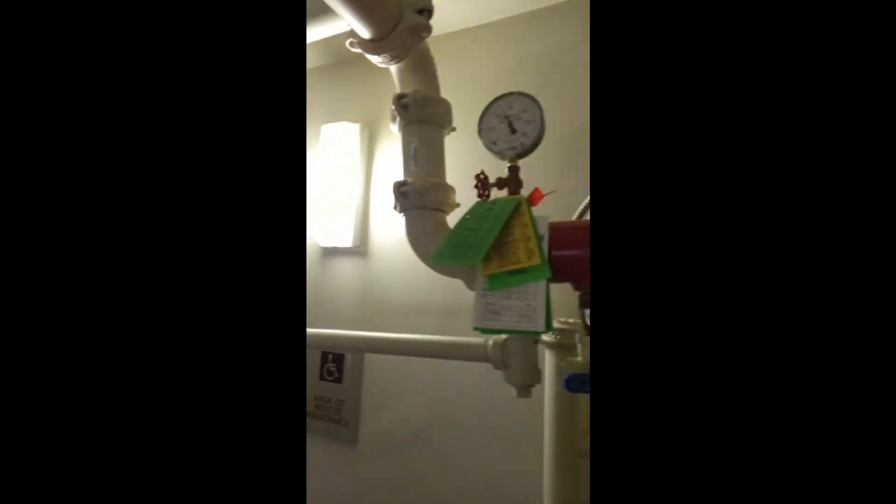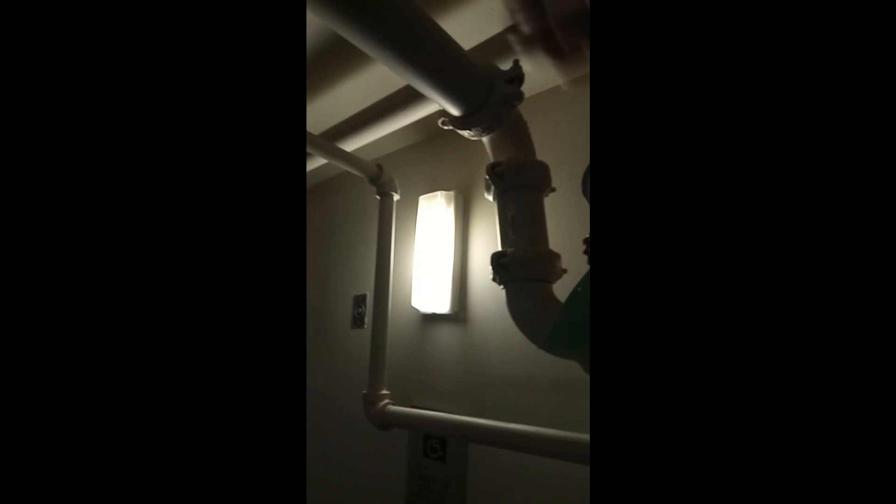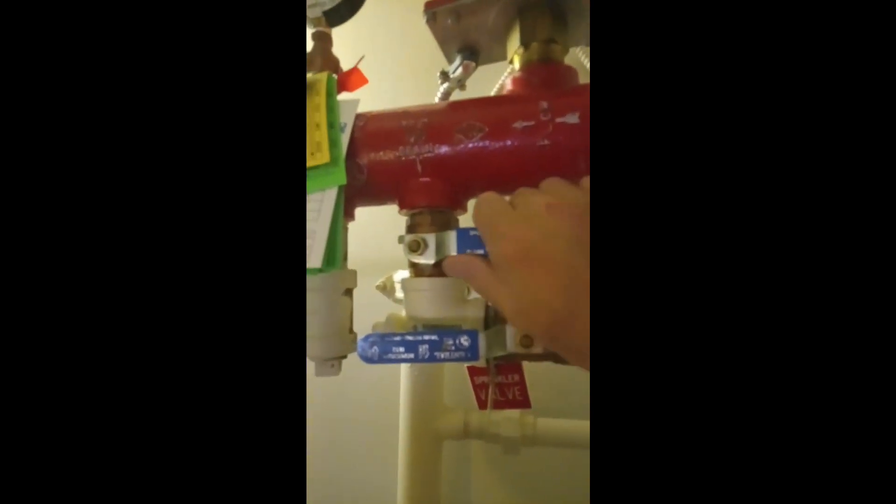At this point you should have all of the shutoff valves closed for your location. There is still going to be a lot of pressure in the water lines even though you have a broken sprinkler head. Therefore, we need to open the drain ball valve. This will allow the water to exit the lines and travel outside of the building. As you turn the ball valve, you will notice the pressure gauge drop all the way down to zero. You can verify that all of the water has drained by looking at the sight glass.